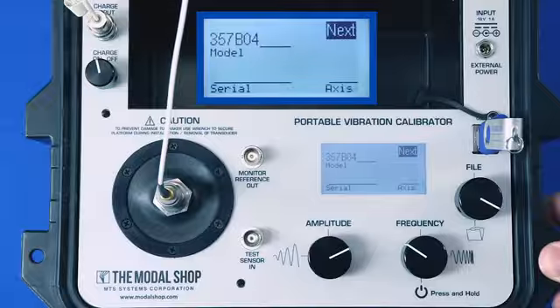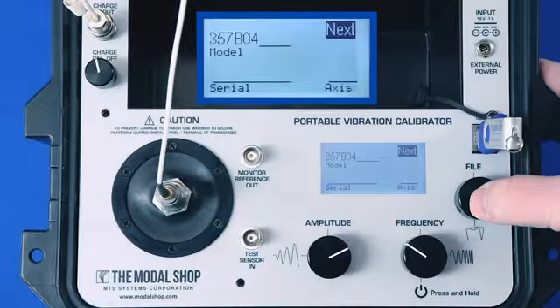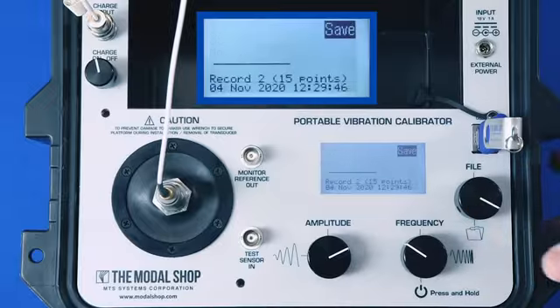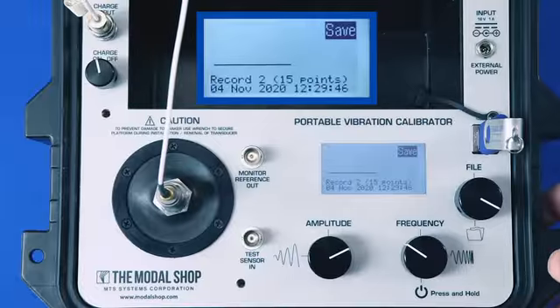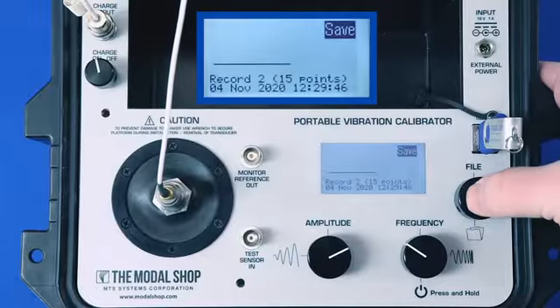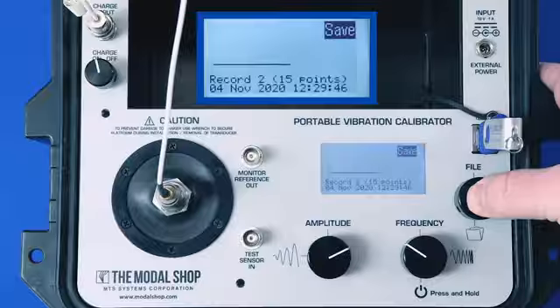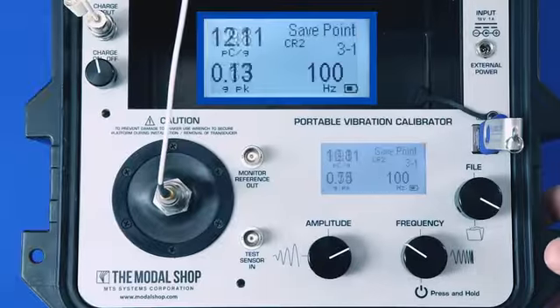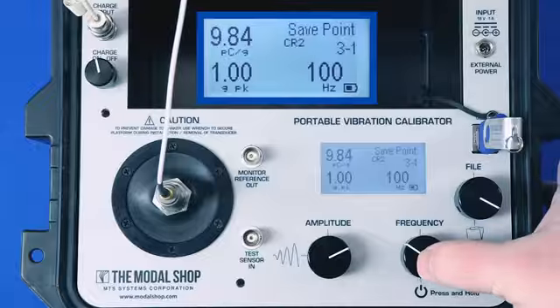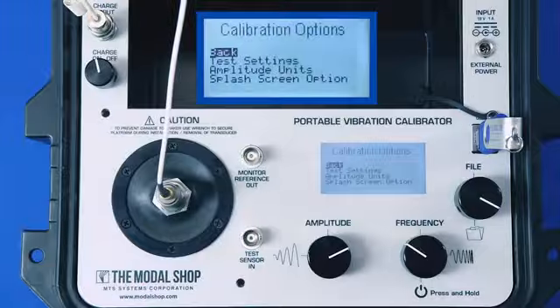All test points passed. Here on this screen we can enter the serial number if we like. I like to do that in the calibration certificate itself, and then we save it to the memory with a date and time stamp, which is ISO 17025 compliant. And we're done. We can pause the shaker and mount another transducer for calibration.